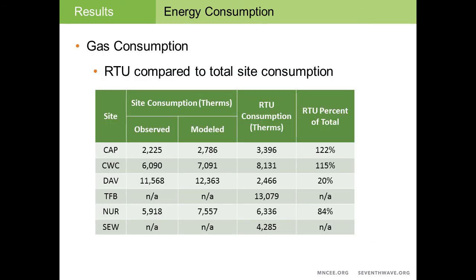So we were able to compute the annual energy consumption from the rooftop unit models. We developed the models with outdoor air temperature and then applied the model to typical meteorological year data, or TMY data. And we were able to look at what the energy consumption was of the rooftop unit as opposed to what the site consumption was. For the site, we used 12 months of energy data, monthly energy bills, and I report here the observed, which is the actual, and then we developed a model and applied the TMY data to figure out what the modeled consumption was.